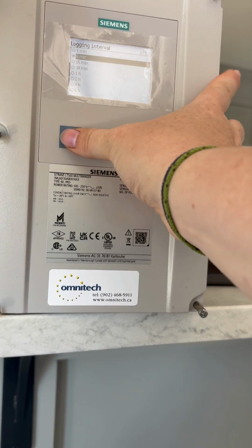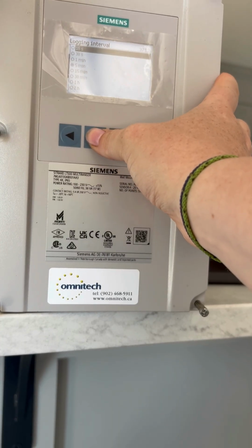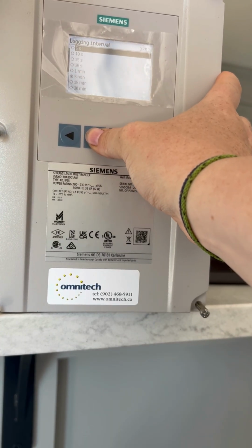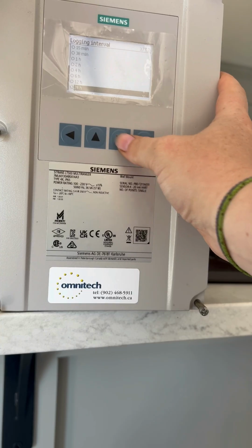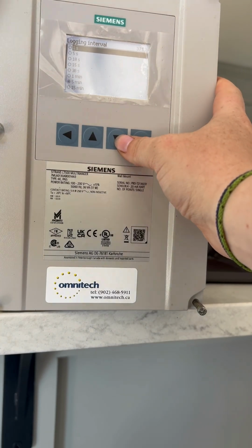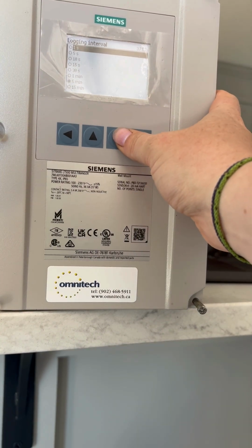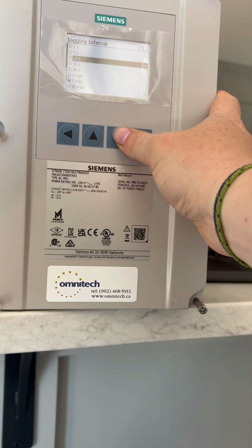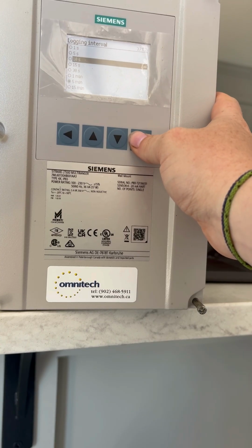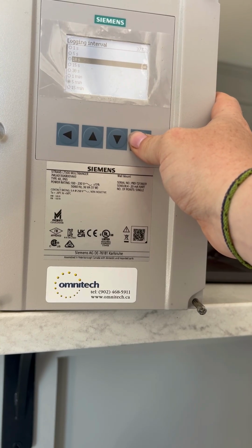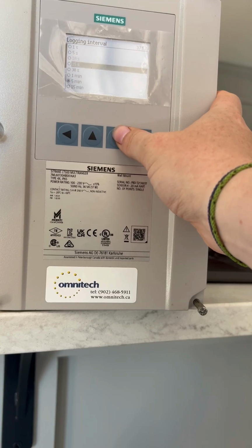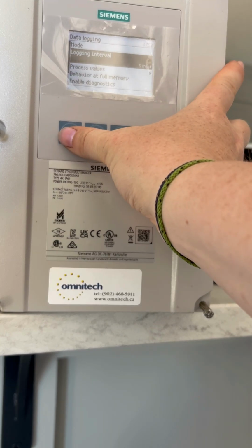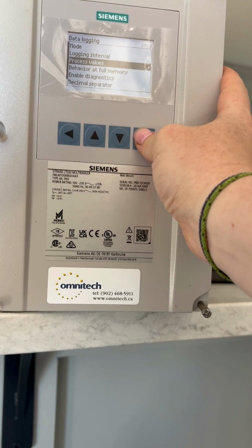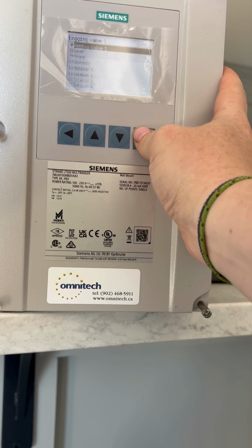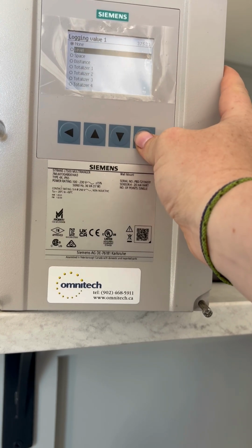It can be set anywhere you want: 1 minute, 30 seconds, 10 seconds, all the way down to every second. I wouldn't suggest that unless you really need that data. But again, if there's a reason to, definitely do that. Just watch out when it gets full, it will stop writing or it will start overwriting. You can enable that as well. So I'm going to keep that on 5 minutes. And my process values that I want, my first value is going to be level.